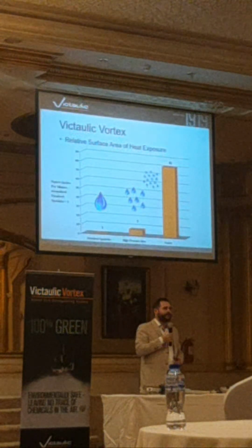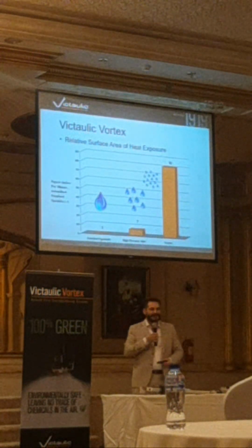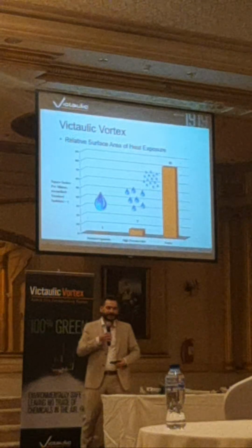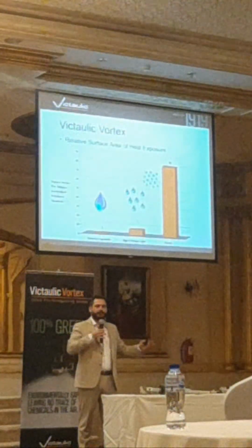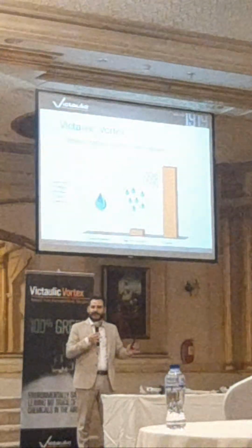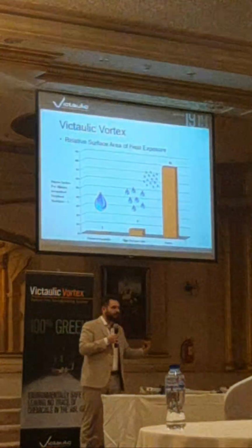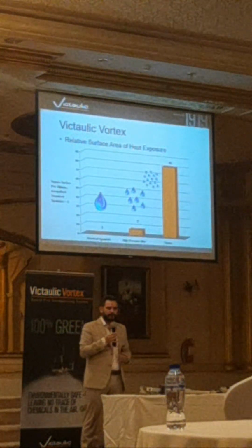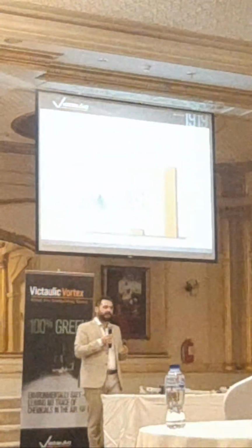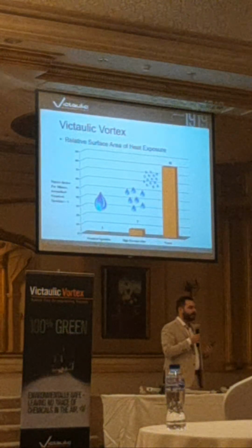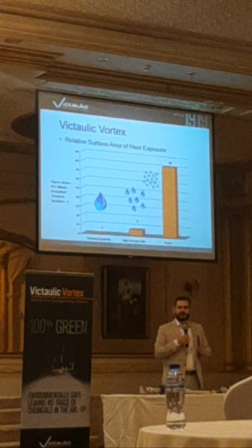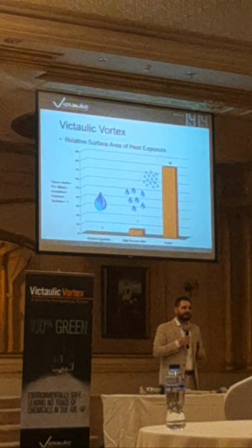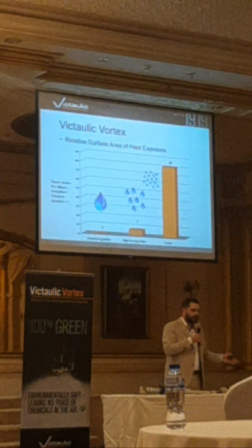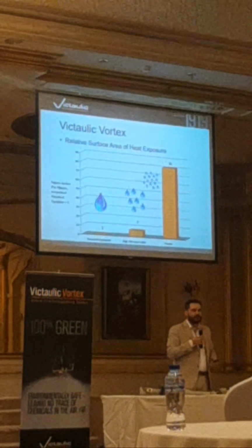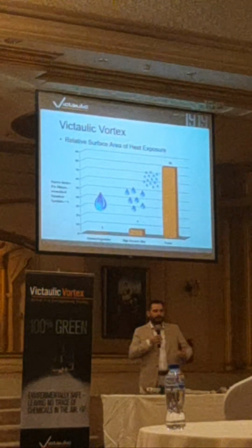We're currently in a very large convention hall, so to estimate how big this would be is hard. So I'll use a volume of 150 cubic meters as an example, which is a standard or relatively small server room. That would need 3 nozzles in total, running for 3 minutes, at 1 liter per minute per nozzle. So we're talking about 9 liters of water, maybe a bucket of water, to protect the 150 cubic meter server room or electrical room.